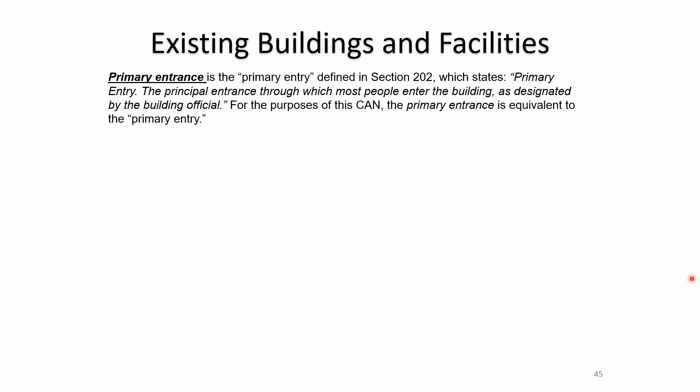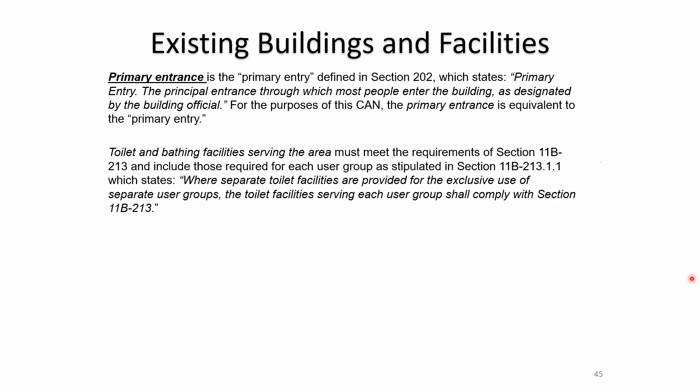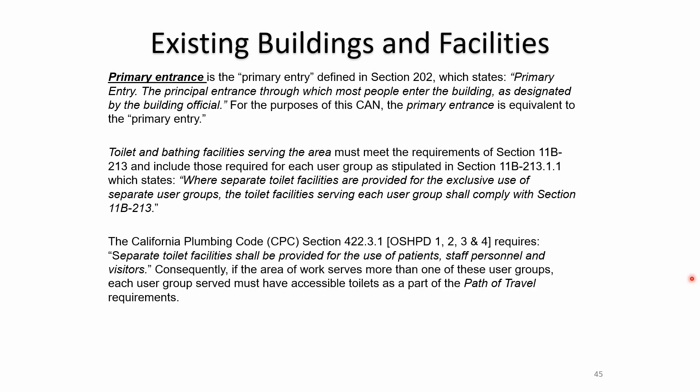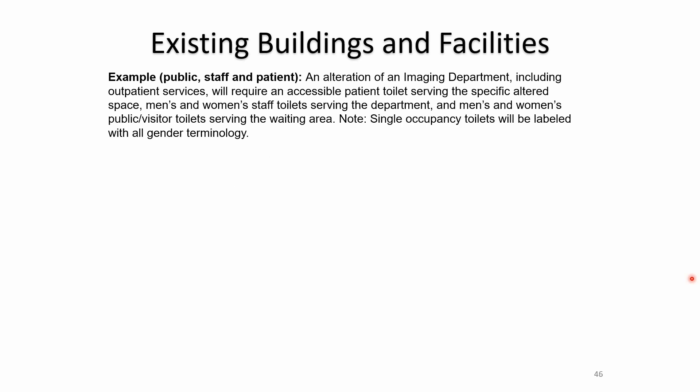If signage on the path of travel to the area of work does not meet the present or previous code, it can be considered for replacement as part of accessible path of travel upgrades. The primary entrance is the principal entrance through which most people enter the building. Toilet and bathing facilities serving the area must be accessible and include those required for each user group. In healthcare, where separate toilets are provided for separate user groups, facilities serving each user group shall comply. The plumbing code requires separate toilet facilities for patients, staff, and visitors.